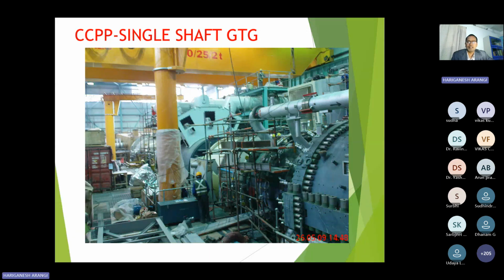This is a combined cycle gas plant. This is the gas turbine area, where a gas turbine is connected with a generator, one setup. In the same plant, a steam turbine will be connected to another generator, which is called multi-shaft or dual shaft. Whereas this plant, which is from Singapore, is a single shaft.